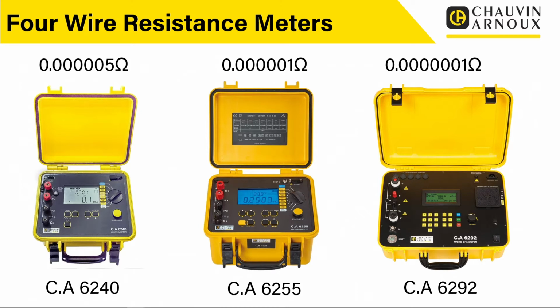This is a different league, as you can see. When we get into 4-wire measurement with the micro-ohmmeters, we start off with, for want of a better term, our most popular but least accurate micro-ohmmeter. This will actually measure down to 5 micro-ohms. So that's 5 millionths of an ohm. So when we were talking about 0.1 or 0.01, this is 0.000005 of an ohm. So again, we're talking really, really small values, and you can see it's a total step change in the level of accuracy that can be achieved. And by doing that, that opens up so many more options for us to get useful information by doing these low resistance measurements.